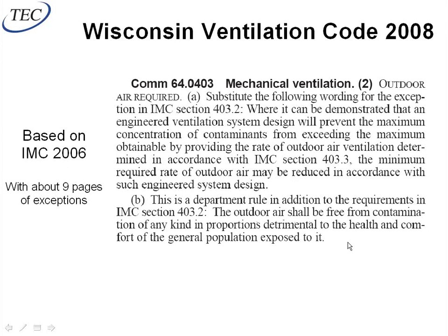So basically it says if you as an engineer can verify and calculate that the amount of ventilation you're bringing in at a given moment is sufficient, then you can do it. And I think by pointing to ASHRAE 62 and the IMC as your design criteria, that's a pretty safe bet that you can point to that as an acceptable engineering method.